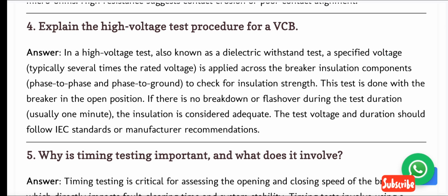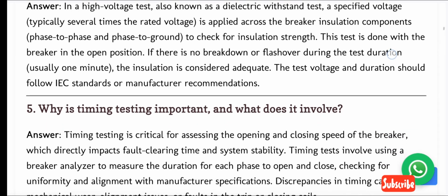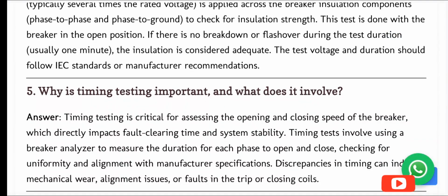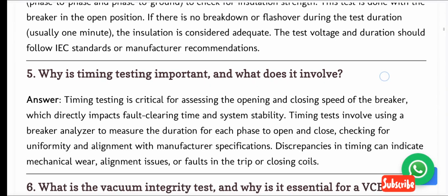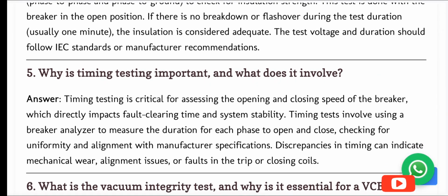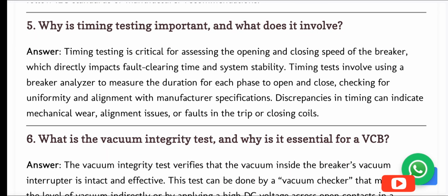Answer. In a high voltage test, also known as a dielectric withstand test, a specified voltage, typically several times the rated voltage, is applied across the breaker insulation components, phase to phase and phase to ground, to check for insulation strength. This test is done with the breaker in the open position. If there is no breakdown or flashover during the test duration, usually 1 minute, the insulation is considered adequate. The test voltage and duration should follow IEC standards or manufacturer recommendations. 5. Why is timing testing important, and what does it involve?